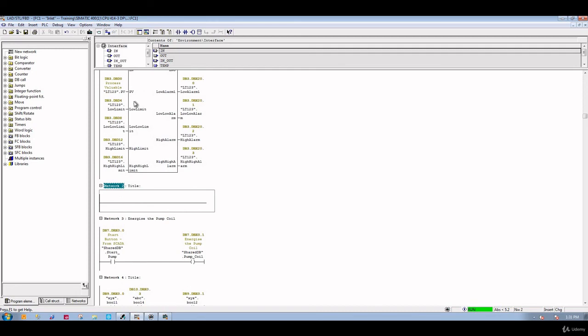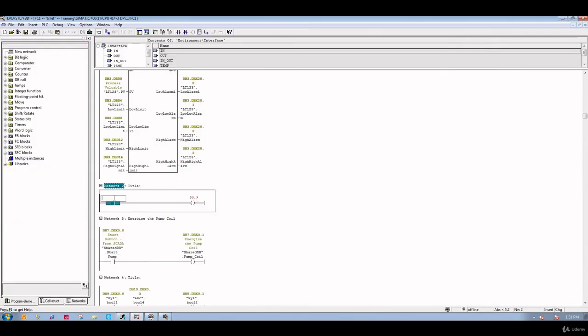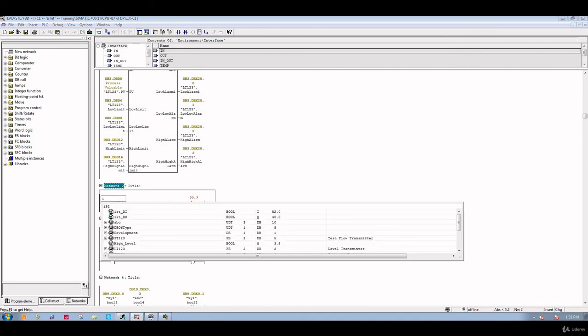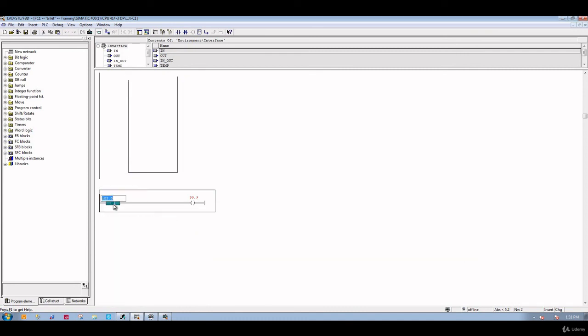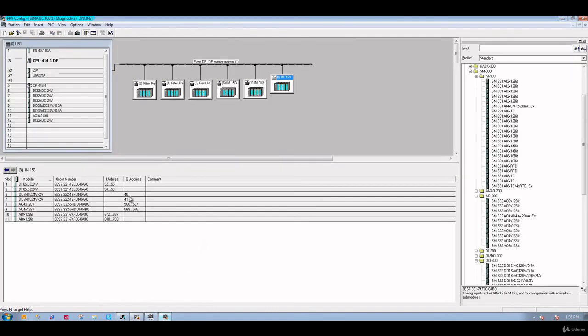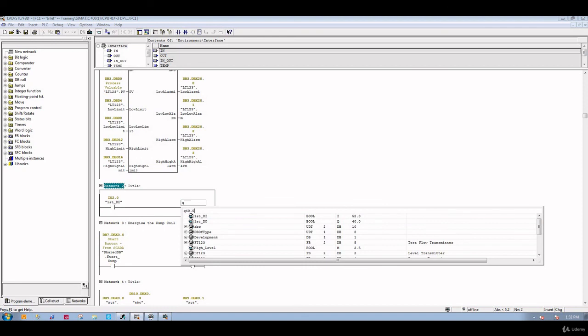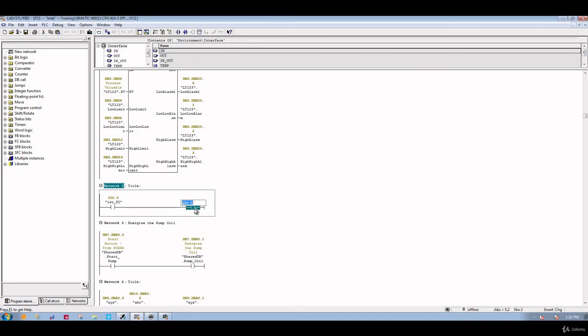I'll add a new network, which has 1 input, 1 output. Our new input and our new output is 52.0. So I52.0. You see, it's phase DI. That's the sample we assigned. And then phase DO is 40.0. So I'll just say Q40.0, phase DO. And then we can just save, download.